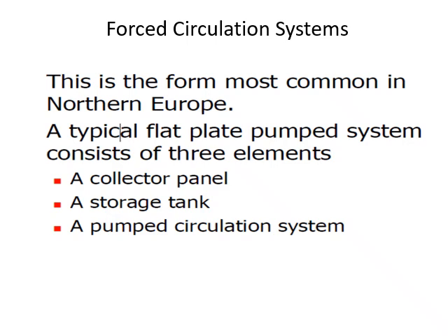And for the thermosiphon system, it goes the same. There's an auxiliary heater because, for example, if it's very cold or there have been cloudy days for at least 2 to 3 days, and you do not get enough sun to heat up the water, we can still use the tank as our hot water supply source, but for that we will need the water heater. So the auxiliary heater will work only when the sun is not there. The forced circulation system, as I have mentioned, has a collector panel, a storage tank, and a pump circulation system.